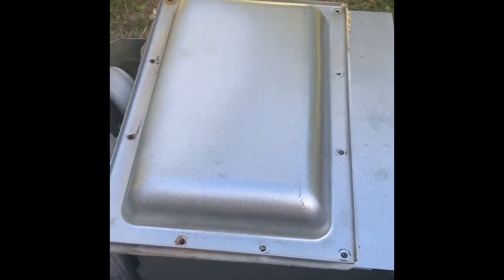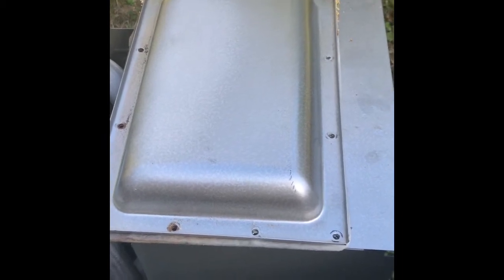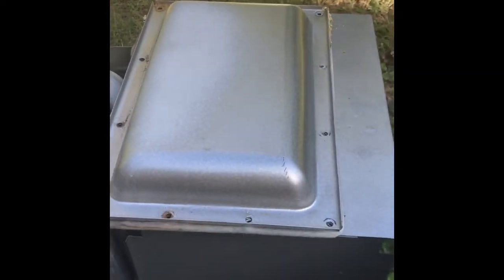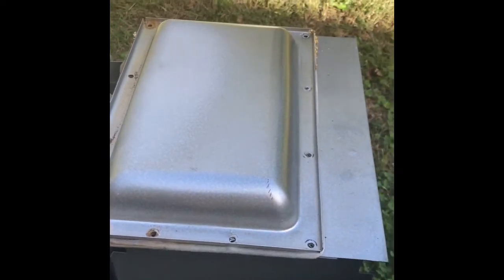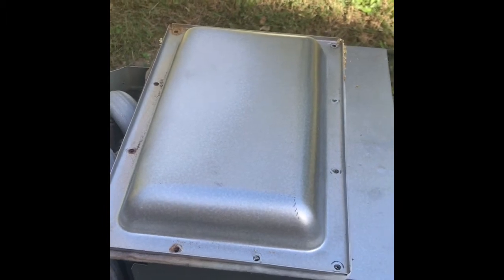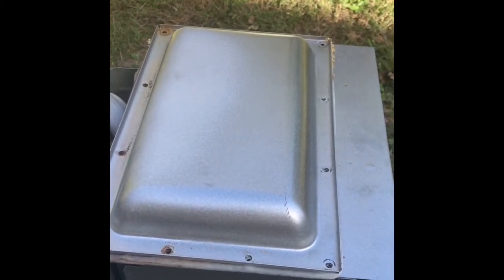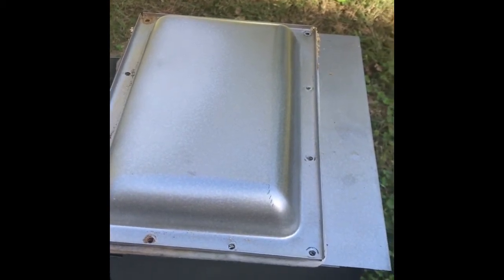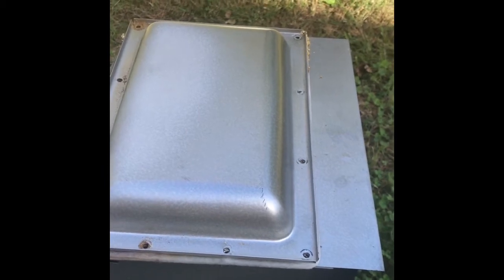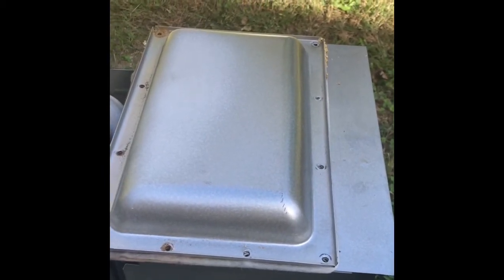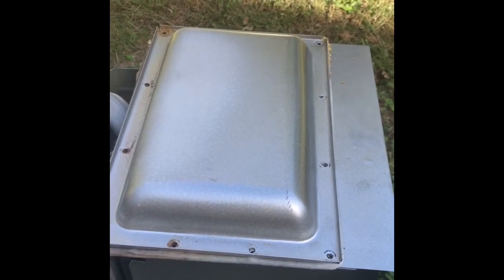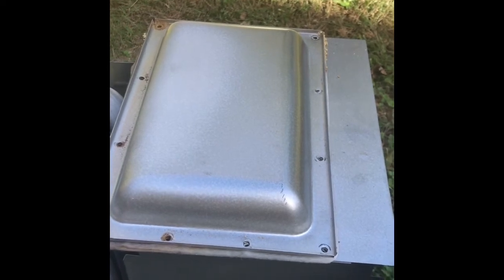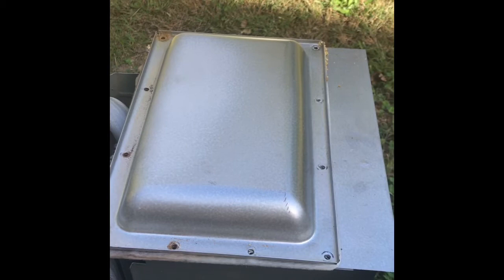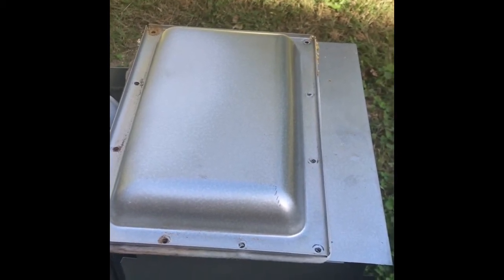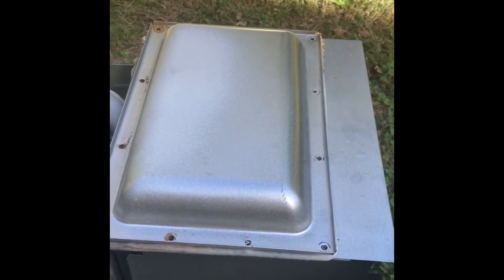Alright, I have all the screws out of the secondary cover at this point. I can tell you that this furnace is on LP, and the regulator wasn't set properly on my first visit out. I adjusted the regulator, and I had to change a gas valve and an igniter. Long story short, I adjusted the regulator to get the pressure up where it needed to be. We were at 9 inches of water column maximum when I arrived. I turned it up to about 12 inches of water column, enough to sustain 10.5 inches to both of my propane furnaces. Yeah, you heard that right, there's two furnaces here, and they were being fed by 9 inches of water column. So if both furnaces were running at the same time, how well do you think they were running?